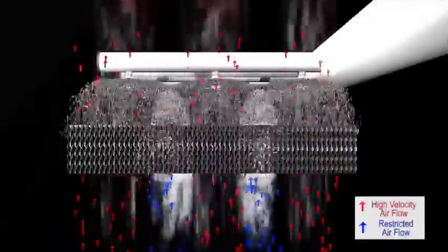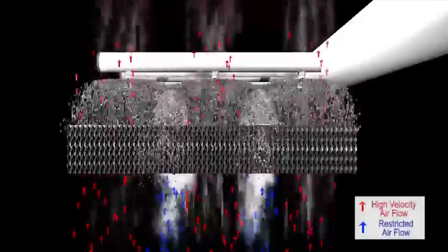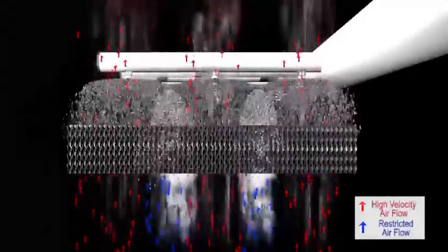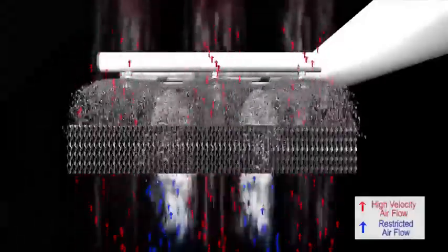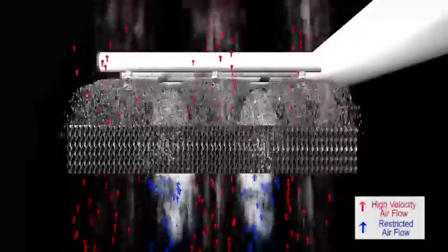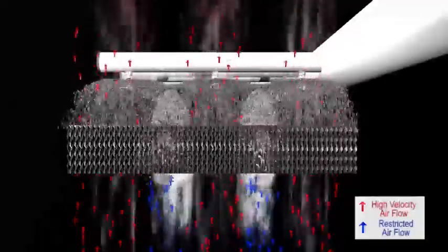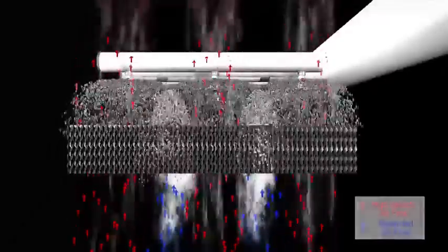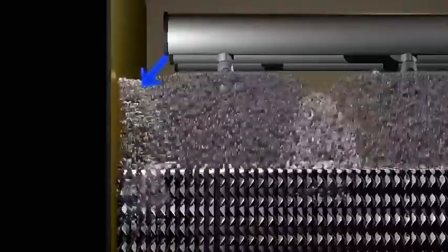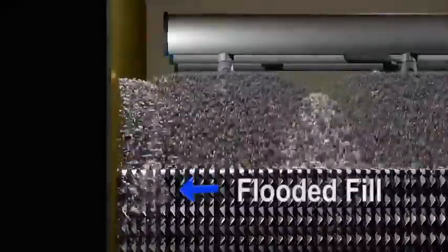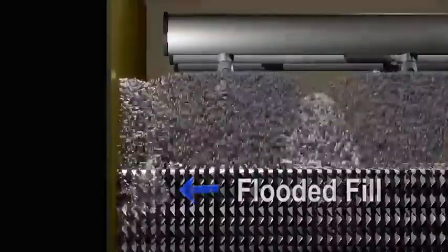Both the volume of air and the velocity will increase in these areas. The red arrows depict the accelerating airflow exiting the film media at high velocities, a gross waste of fan energy. The same circular water pattern of the spray nozzles hits the walls on the perimeter of the cooling tower, flooding the film media in these areas.